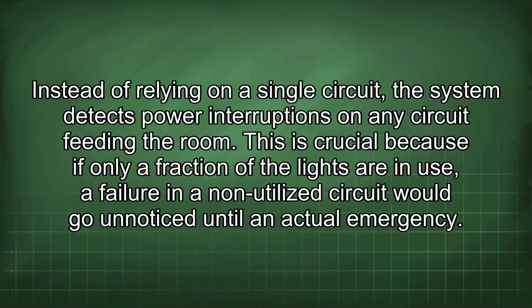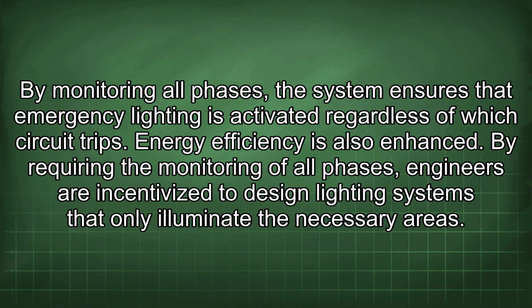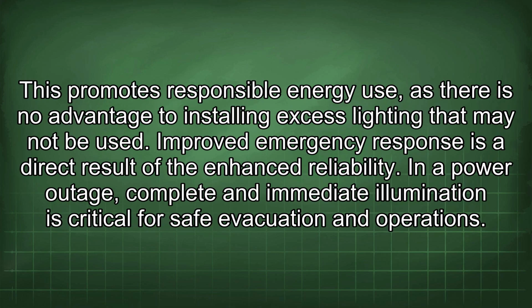Instead of relying on a single circuit, the system detects power interruptions on any circuit feeding the room. This is crucial because if only a fraction of the lights are in use, a failure in an unutilized circuit would go unnoticed until an actual emergency. By monitoring all phases, the system ensures that emergency lighting is activated regardless of which circuit trips. Energy efficiency is also enhanced. By requiring the monitoring of all phases, engineers are incentivized to design lighting systems that only illuminate the necessary areas. This promotes responsible energy use, as there is no advantage to installing excess lighting that may not be used.